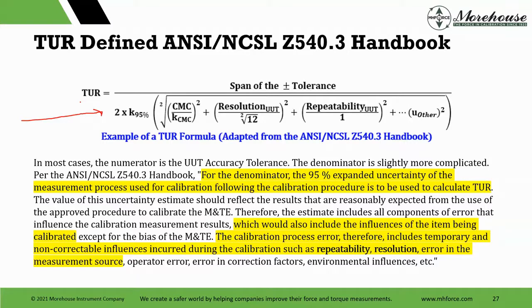So we captured it. If we go to ILAC P14 section 5.4, people can look at this one. I don't have it in the slides, but it talks about short-term contributors. Those short-term contributors in general are going to be: how good was the standard used for calibration? What is that calibration and measurement capability? Hey, what's the resolution and what's the repeatability of the UUT? That's the basics, right? And people may say, oh, well, you don't need to account for the resolution. Well, you might not need to put it in there, but the only way you don't need to put it in there is if your repeatability is the dominant contributor. Because manufacturers will give you specs where the accuracy is the same as the resolution.